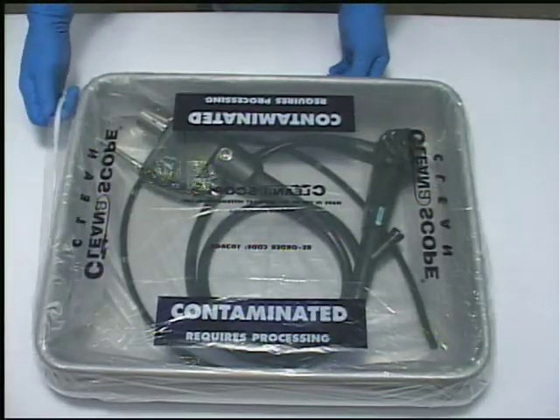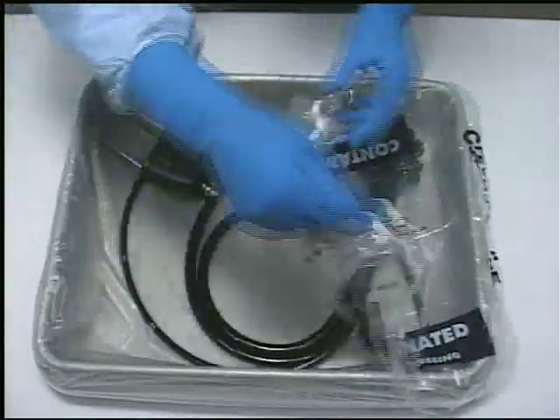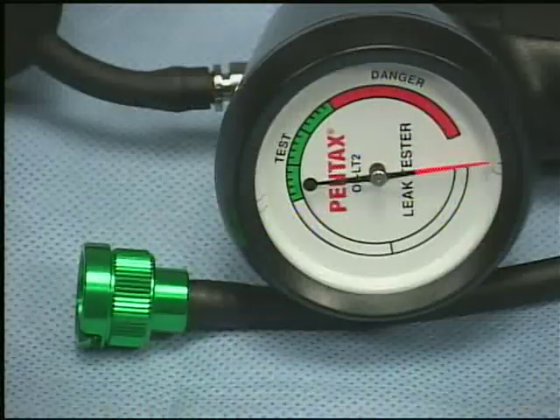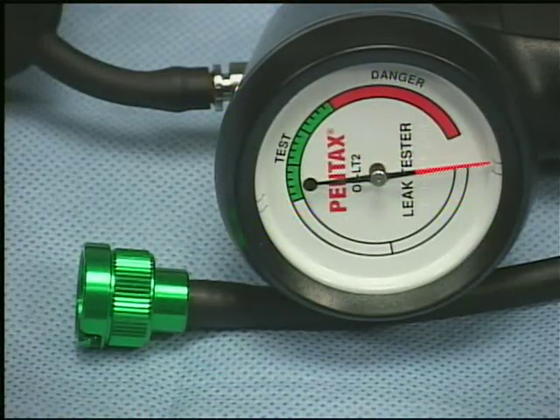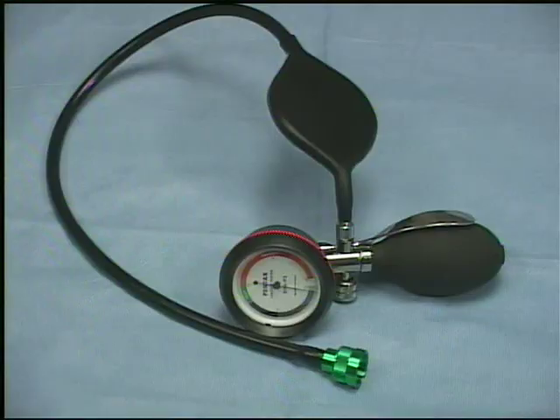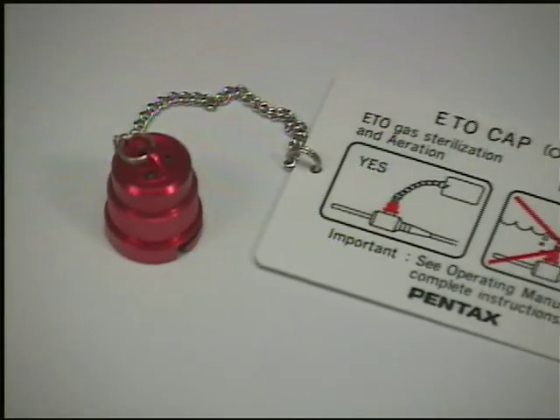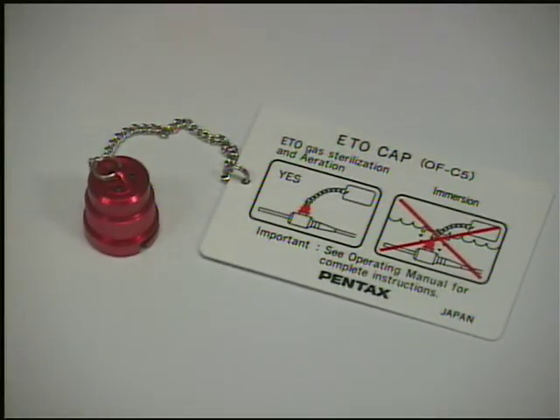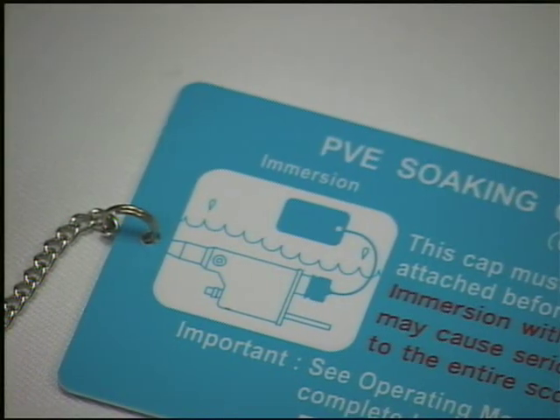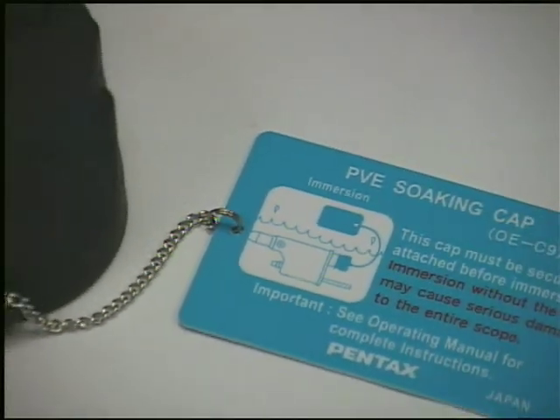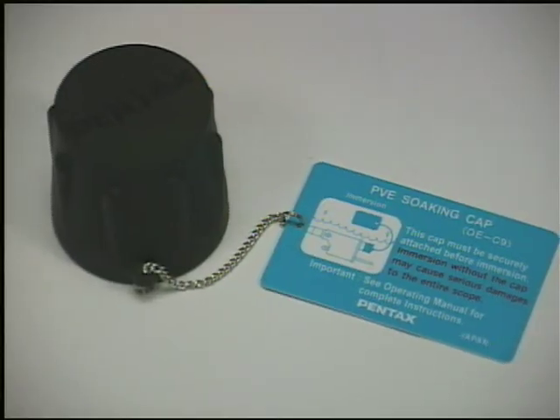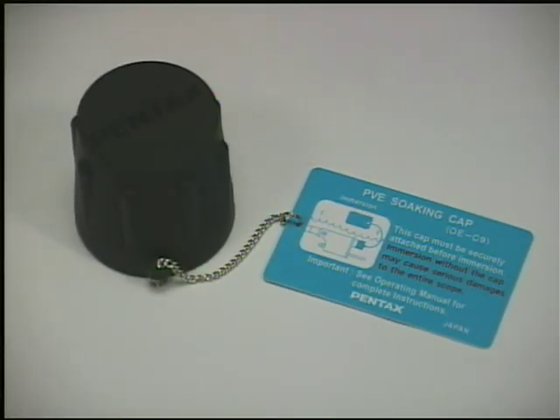Before proceeding with any further cleaning steps, the endoscope must be leak tested. The Pentax leakage tester allows for a simple two-stage testing of the watertight integrity of Pentax endoscopes. Air pressure is delivered by means of a hand-operated bulb, eliminating the need for any electromechanical devices. Always ensure that the red ETO gas sterilization cap is off and the appropriate soaking cap is attached to the endoscope over the electrical contact pins prior to any immersion in fluids.